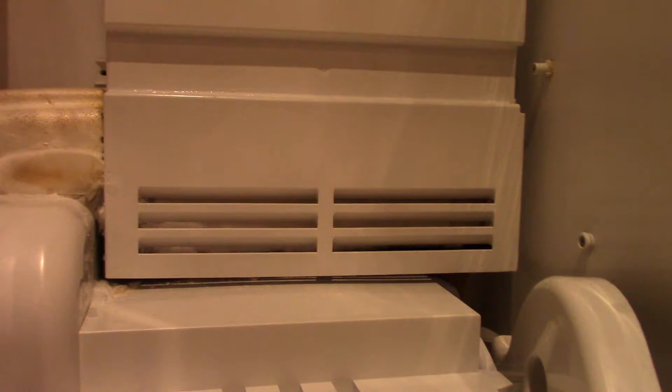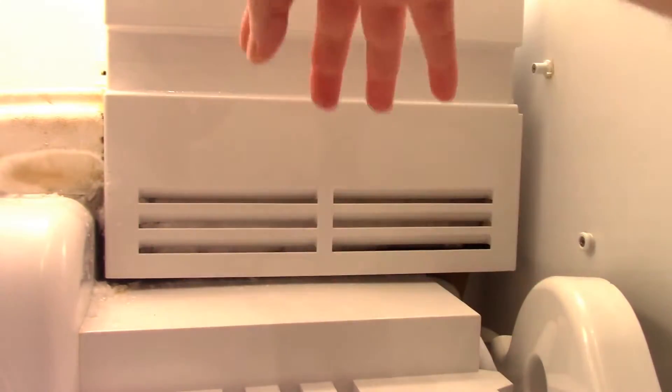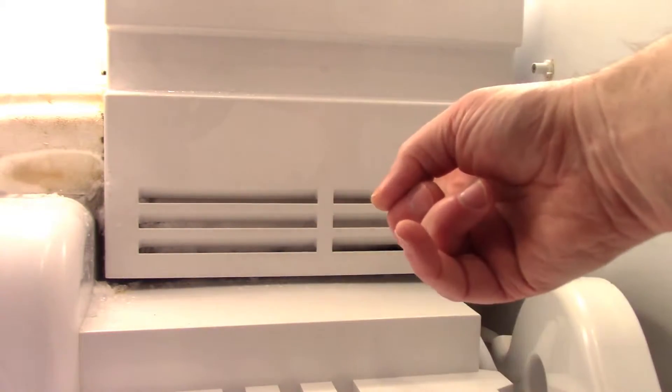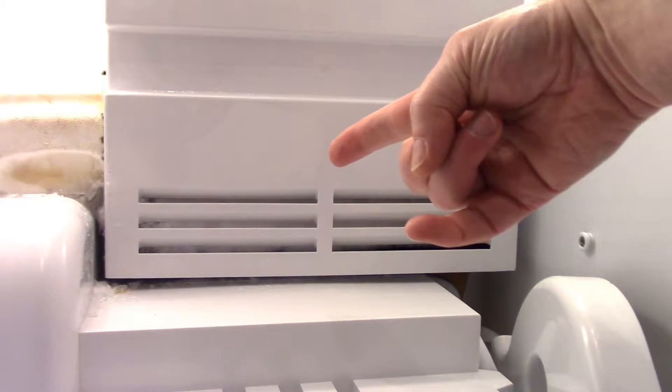The fan is running, but what the problem is, is the evaporator is frozen solid so it can't pull any air across it and up through the tunnel. Now the question is why is this evaporator frozen solid? My guess is the temperature sensor is shot.